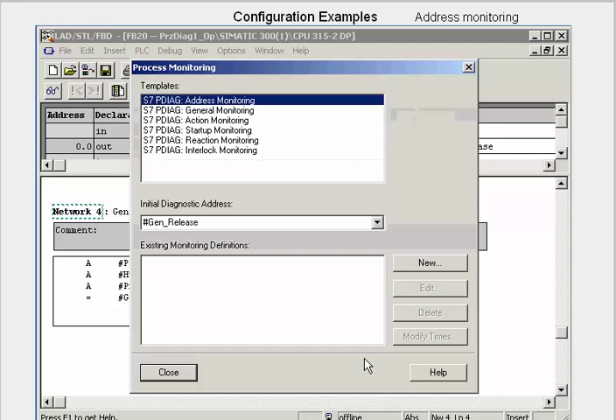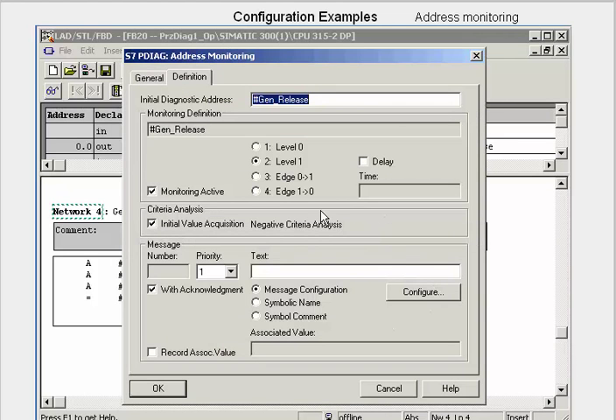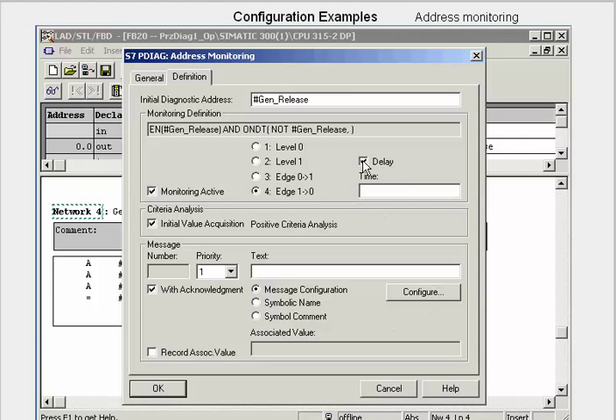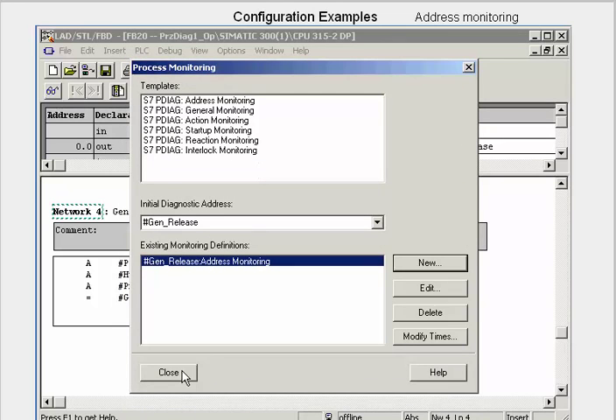Via the New button, we want to configure an address monitoring. In the next dialog, we parameterize the monitoring of a falling edge, enter a delay time of one second, and the message text. The formal parameters in the message mean that when there is a fault, the faulty unit and all the signals concerned are displayed in clear text. We acknowledge the dialogs and save FB20.